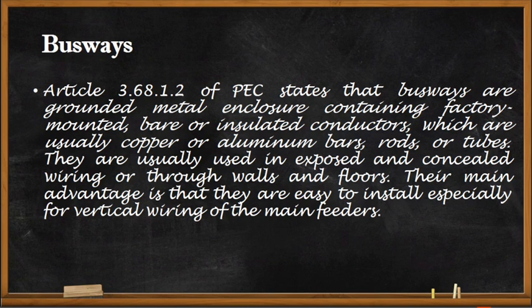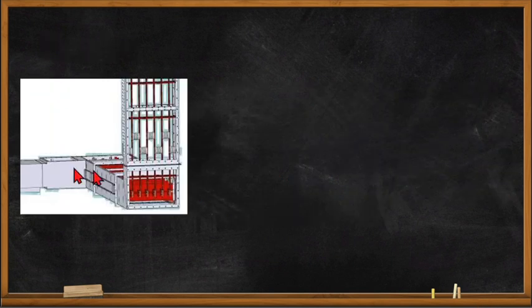The main advantage of busways is that they are easy to install, especially for vertical wiring of the main feeders — for example, in high-rise buildings. A busway is a grounded metal enclosure containing factory-mounted bare or insulated conductors — either copper or aluminum bars, rods, or tubes — and its main advantage is ease of installation for vertical main feeder wiring in high-rise buildings.